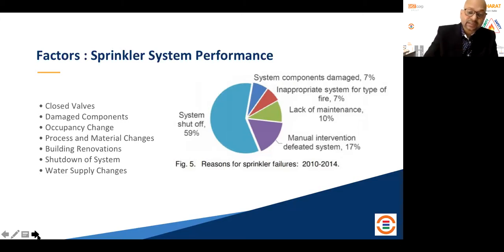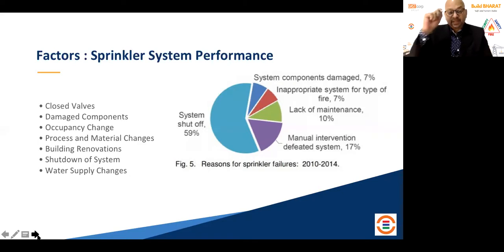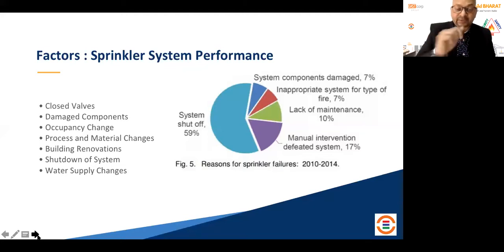Even if you look at the largest reason, it is shut-off systems, that means you close the valve itself on the sprinkler system, at 59%. And I can tell you, in most of the metros, in high-rise buildings with multiple occupants, this 59% will be applicable to those occupancies where the valve is kept closed and is not monitored by the fire alarm system. So in case of fire, your sprinkler system will not discharge water because it is closed manually.